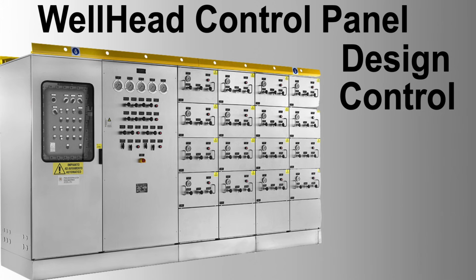Operational and maintenance aspects. Operational aspects. 1. Regular monitoring. Continuously monitor pressure, temperature, and flow parameters. Use HMI SCADA systems for real-time data visualization and control. 2. Alarm management. Set appropriate high and low alarm thresholds for critical parameters. Ensure alarms are promptly addressed to prevent system trips or failures. 3. Manual overrides. Provide manual override capabilities for emergency situations. Train operators to use manual overrides safely and effectively.